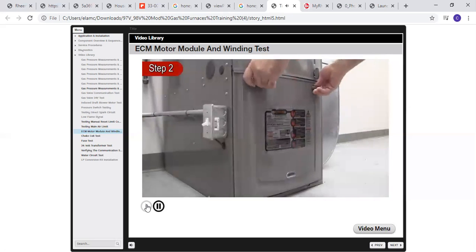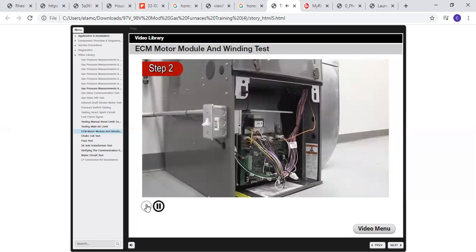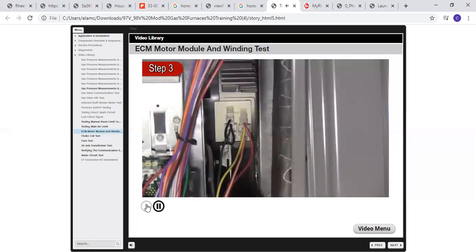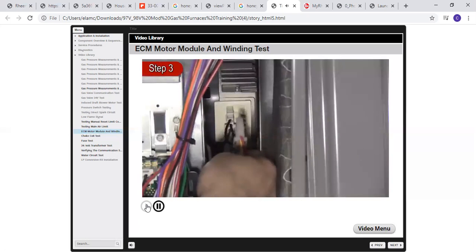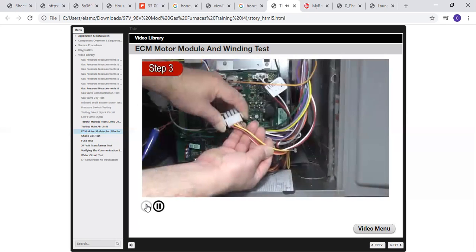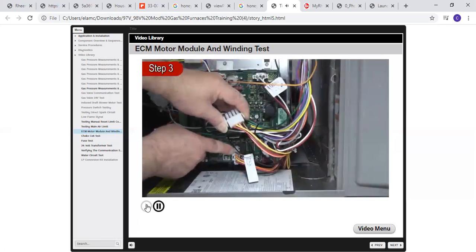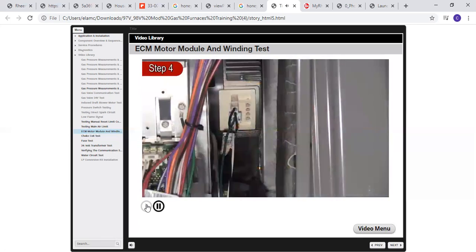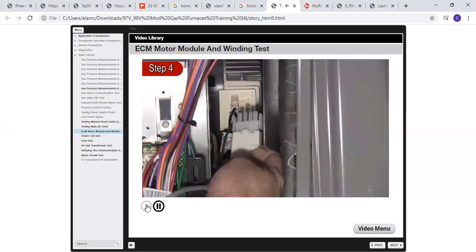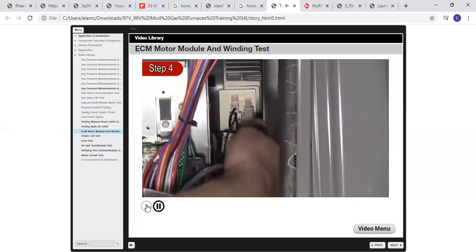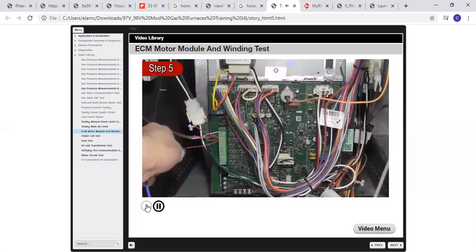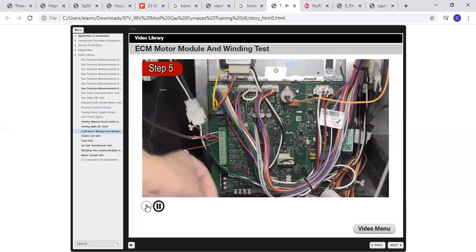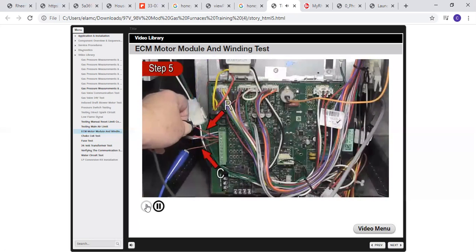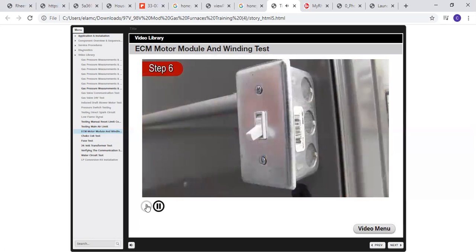Step 2. Remove the bottom furnace panel to gain access to the blower motor. Step 3. Unplug the 4-pin connector at the ECM motor. This connector is the motor end of the harness that leads to the furnace circuit board plug P5. Step 4. Plug the 4-pin Tech Inspect tool plug into the ECM motor. Step 5. Connect the low voltage Tech Inspect clips to 24-volt power. Step 6. Restore power to the furnace.